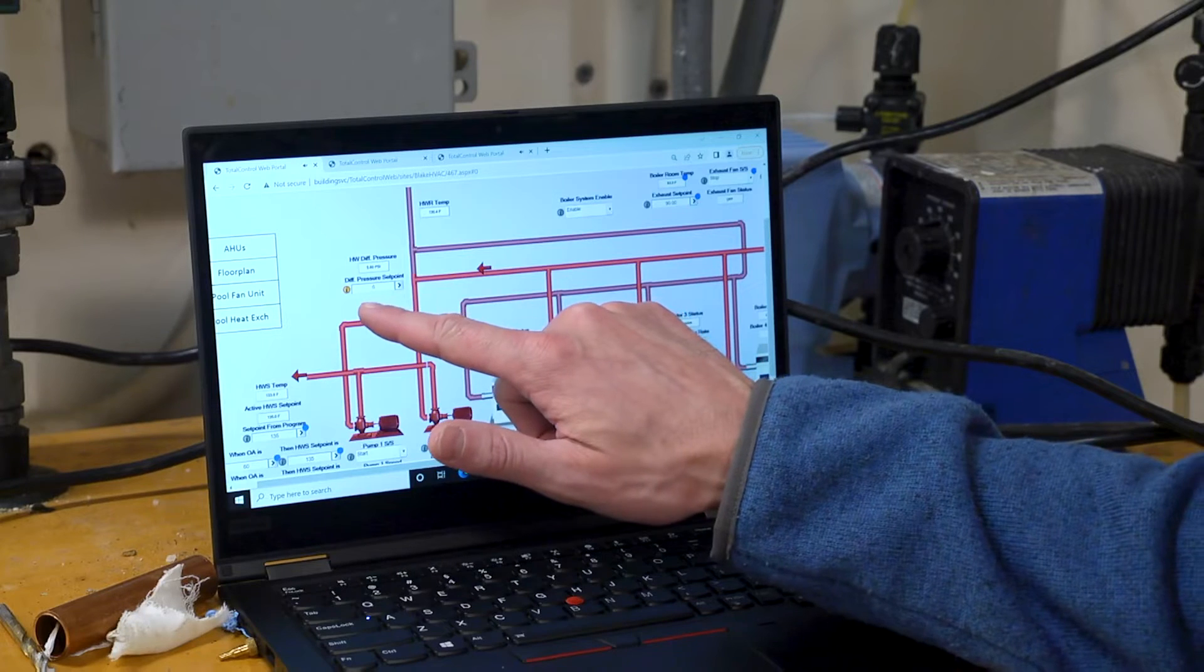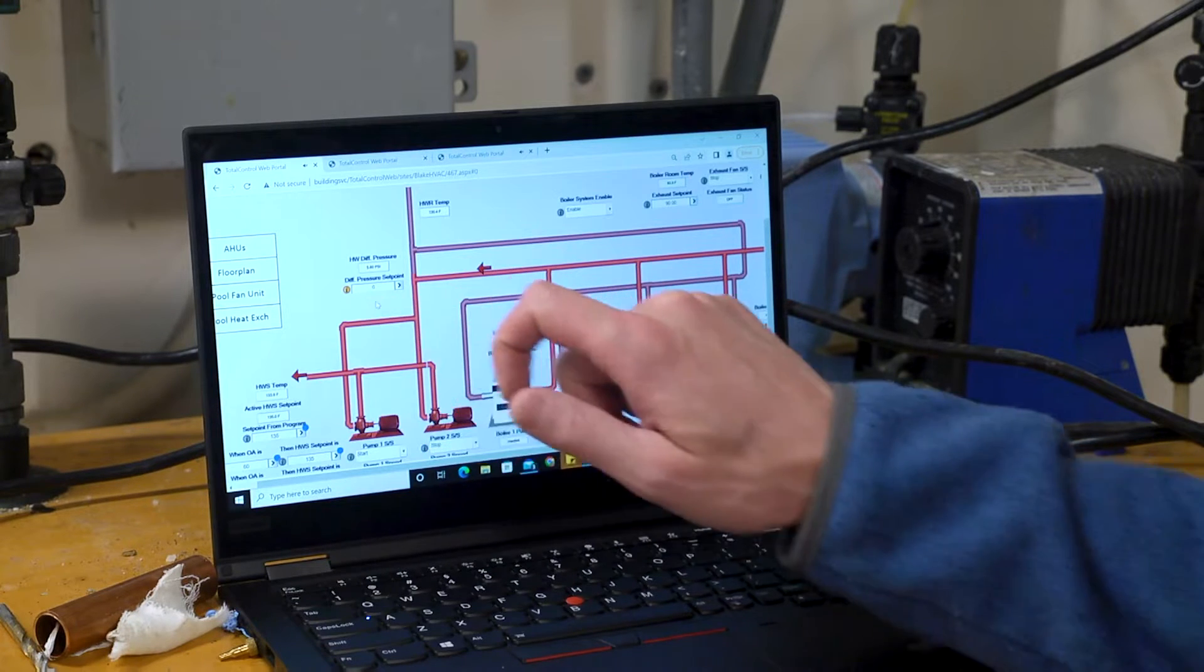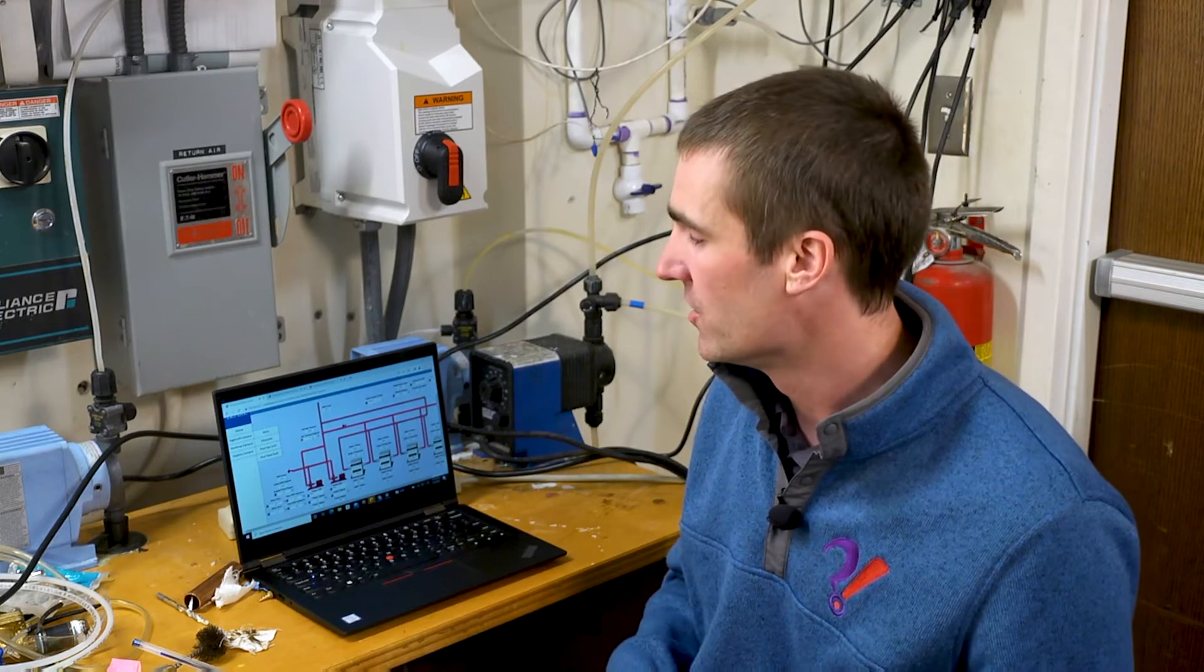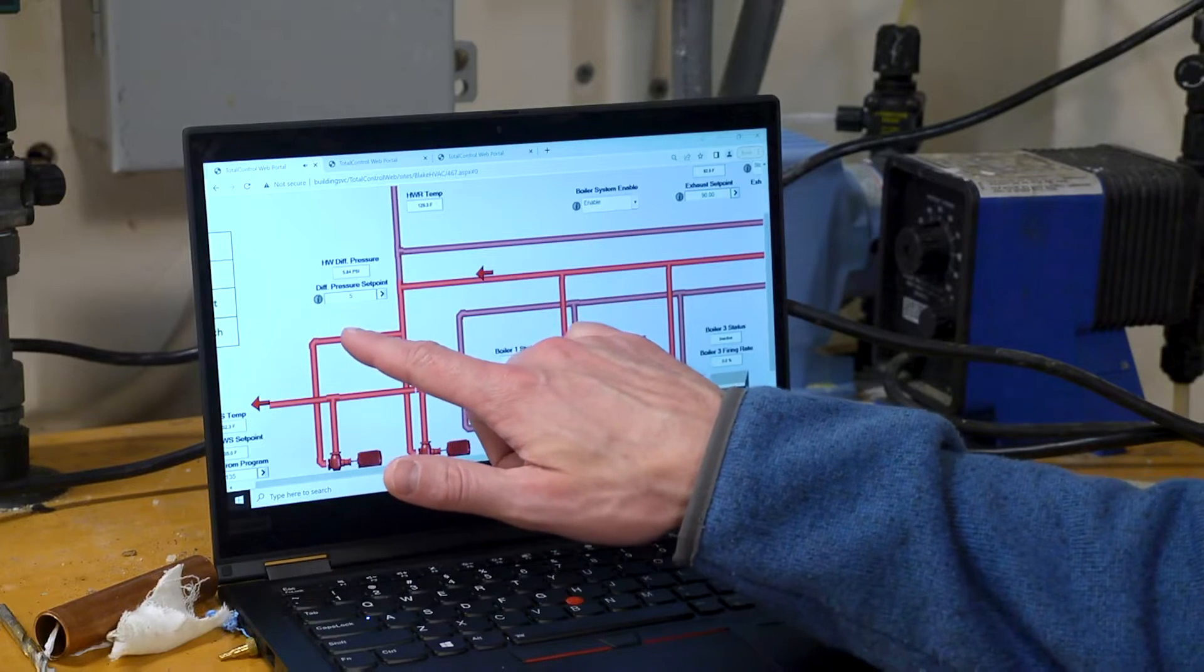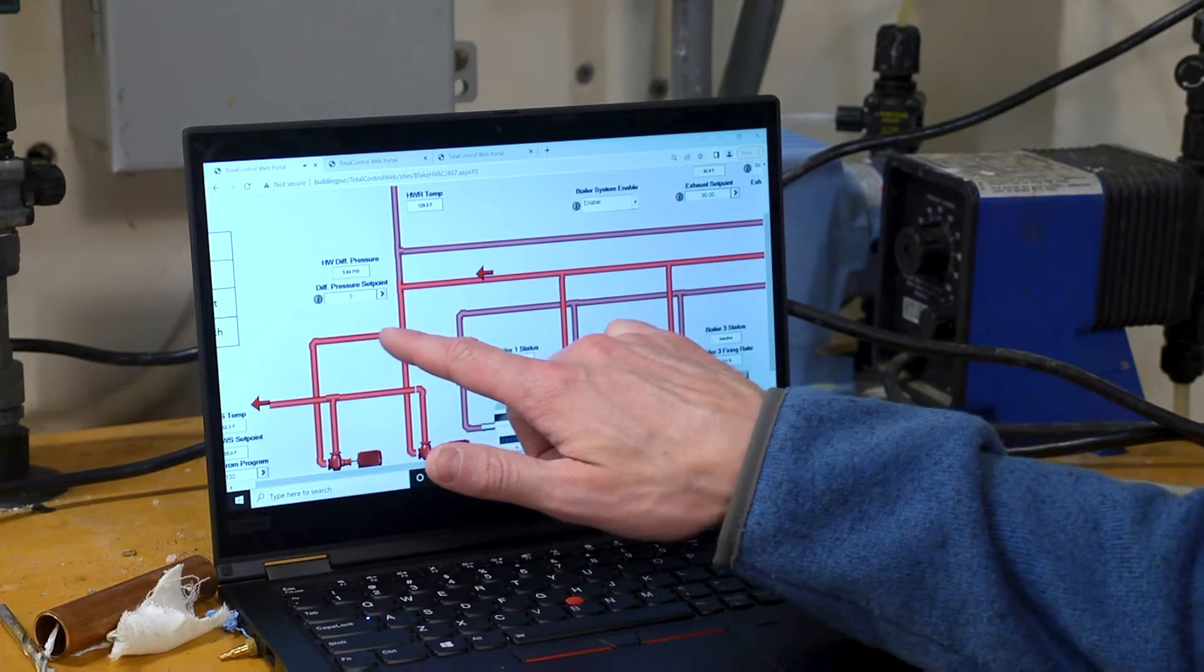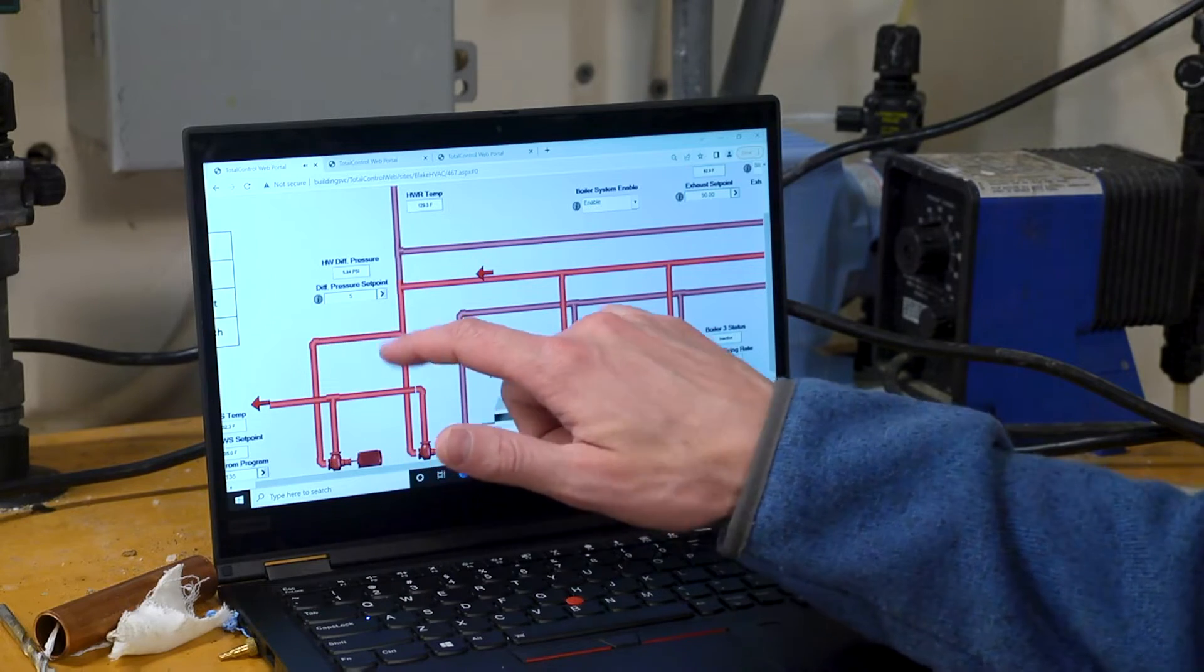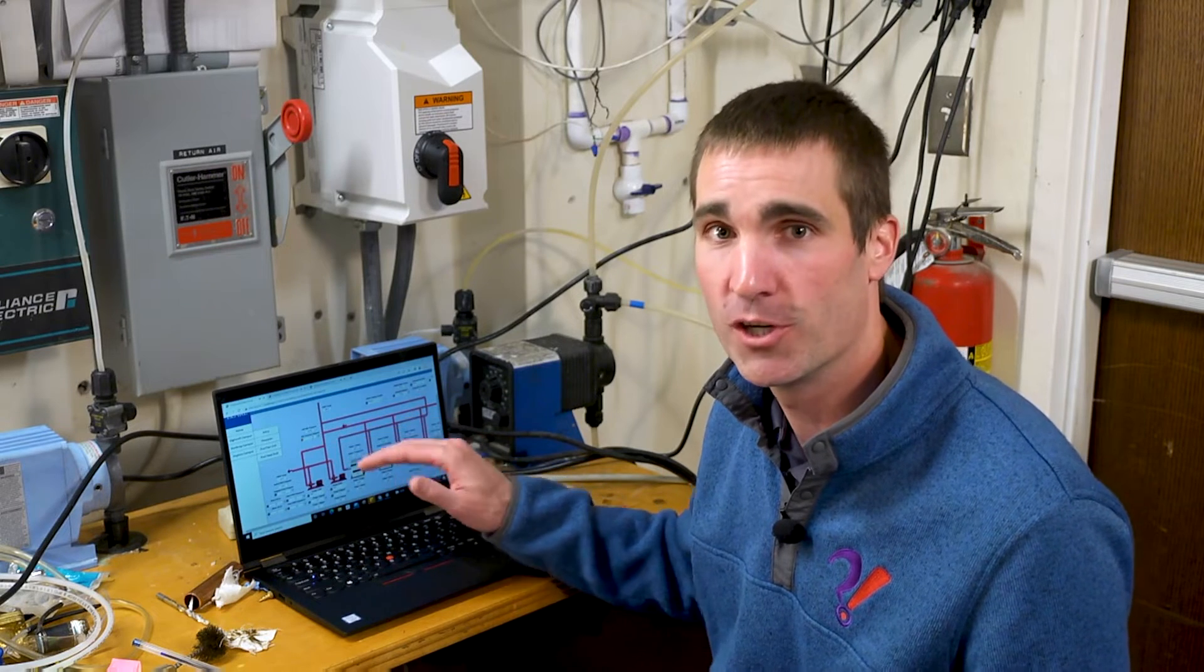They're going to send a flag to the building operator and say you're probably not operating at the correct differential pressure set point. That's an awesome feature of this particular building automation system. They don't all have it. So there's other ways to communicate what the appropriate value is to the building operator. One way would be to add text next to every set point saying what the appropriate value should be. And during their weekly or daily reviews of these screens, they can compare set points to what the values should be and make adjustments as necessary.